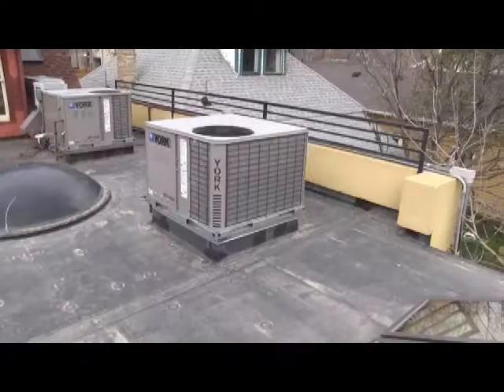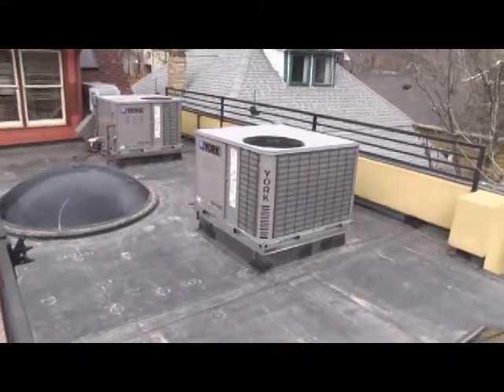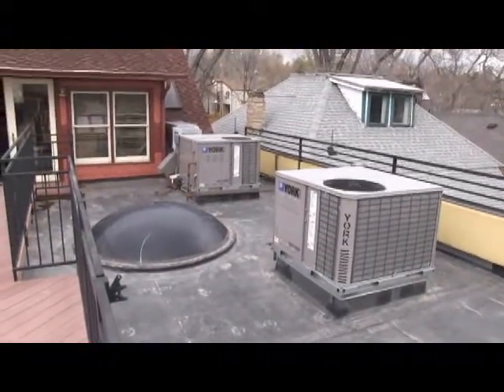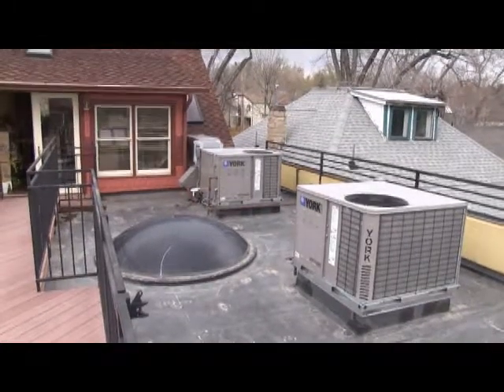And what we have instead is when we took out the old monster 70% HVAC unit, and broke it down into two SEER-rated higher efficiency units, one of those units is dedicated to this room. So there's a touchscreen Honeywell control just for this room, because people come into this room just for an hour or two at a time. We can just pump a little cool air or hot air into this room as needed, and it turns out to be a very efficient solution for this particular room. And then we're not heating it all the time. So that ends up to be a high efficiency solution for this particular room in terms of the HVAC.